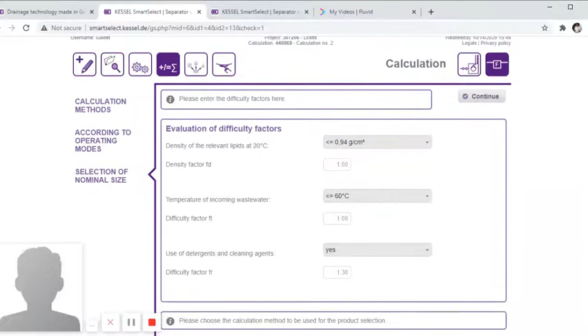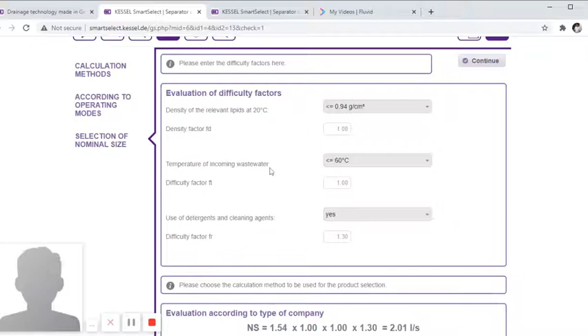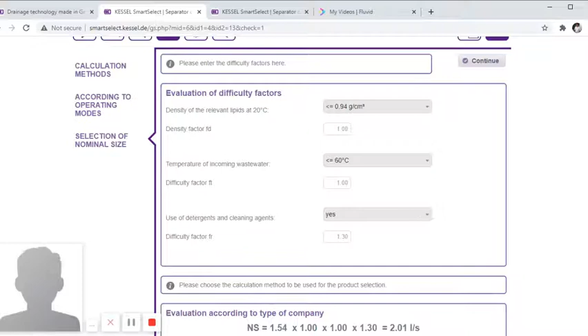Going to the next, difficulty factors will also be applicable as per temperatures, the cleaning agent we use, or the temperature of incoming wastewater. Yes, in our kitchen we use cleaning agents like soaps or sometimes detergent, so this 1.3 factor will be applicable. After the factors, it comes to around 2.01 liters per second. The app is saying NS3 is the right model we can go with. Suppose you want to go with NS3, you just have to click apply.